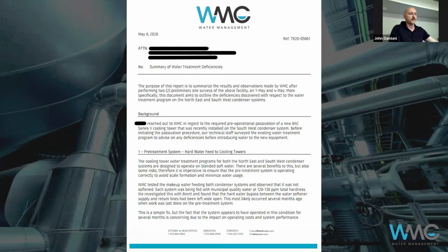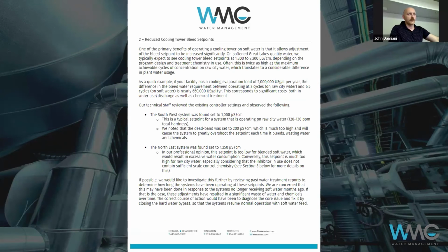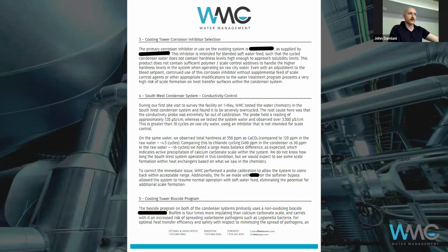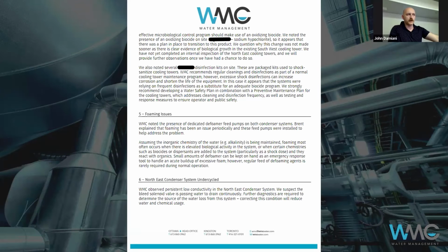So we often work together with them. This is an example of a deficiency report. On this system, we clocked that they've got reduced bleed set points on their cooling towers to try and compensate for other problems. The selection of their inhibitors was incorrect, there was poor conductivity control, the biocide program was having problems, they had foaming issues, and an undercycled system.